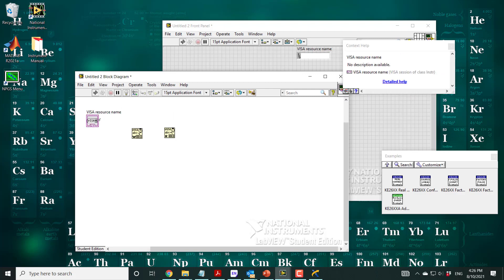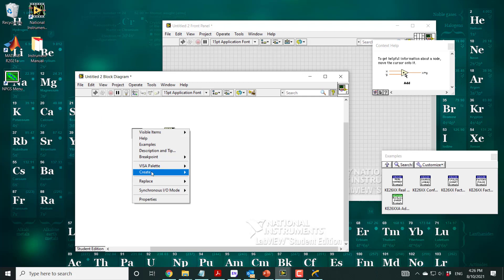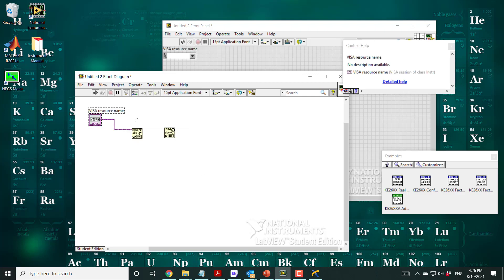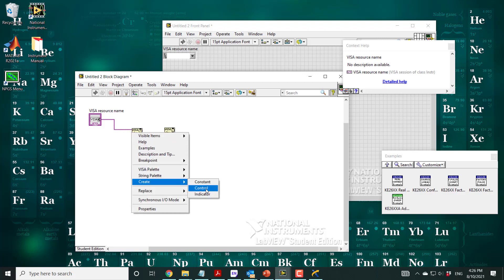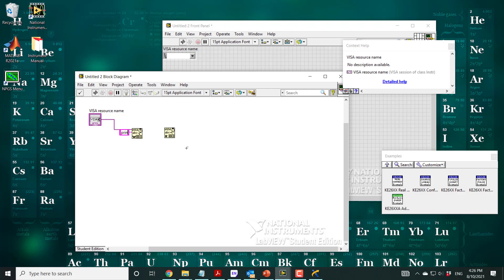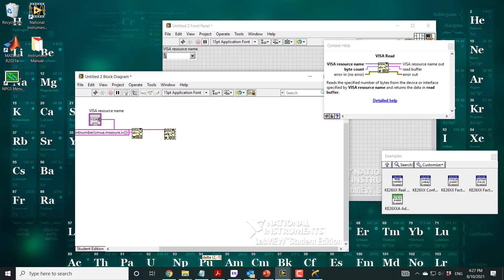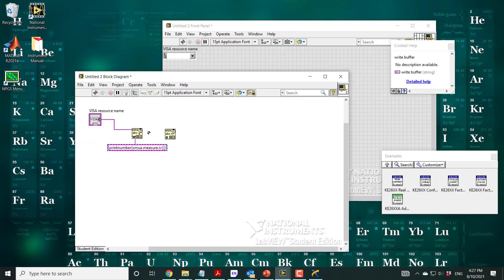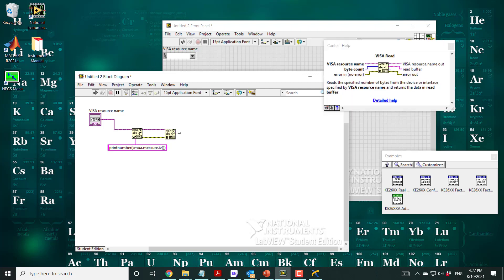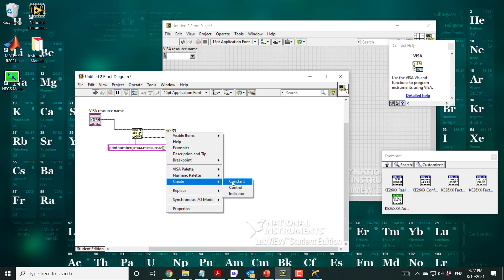We create a control for the VISA resource, and we write a command using a string constant — the command is 'print' followed by 'smua.measure.i'. The 'print number' is the command from the service menu, and 'smua.measure.i' is also listed in the menus. You get this command and send it into the system. All instruments have this kind of programming instruction listing what the commands are — some are more intuitive, some less, but you just send them.